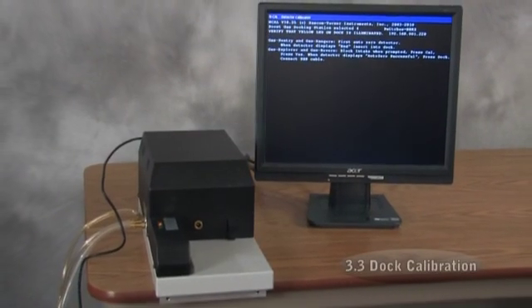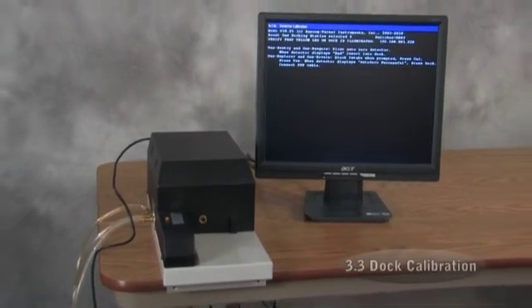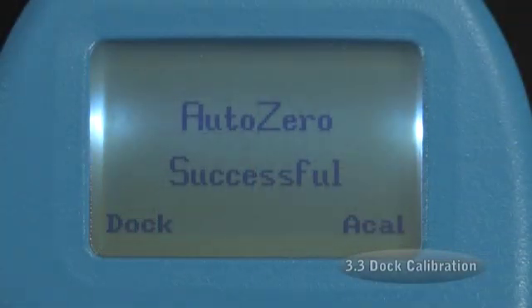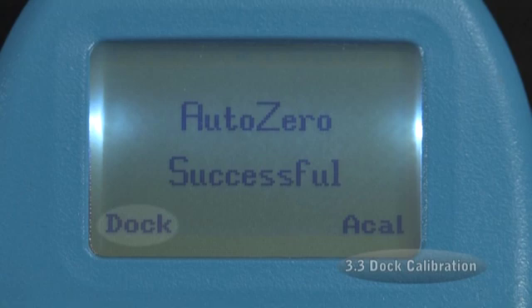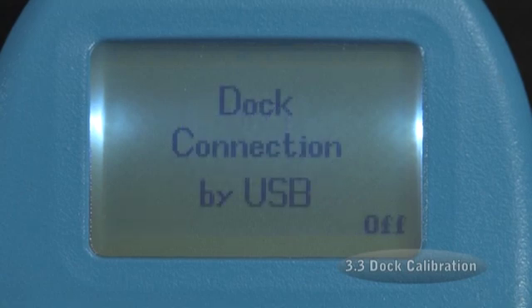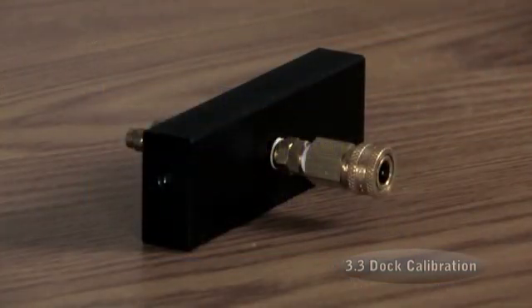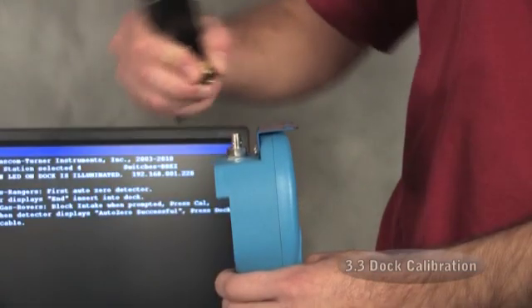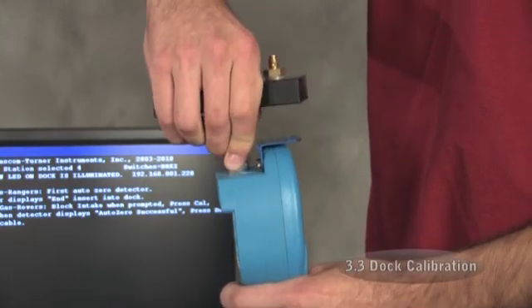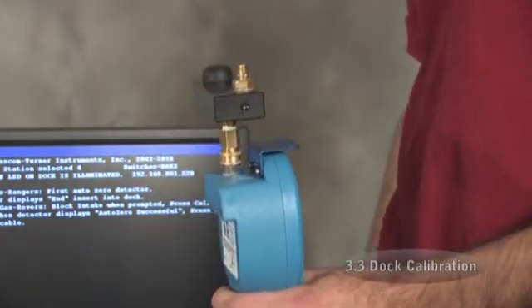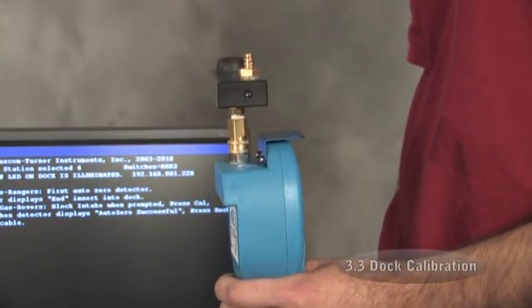Now we'll calibrate the Explorer using a docking station. Once the Auto Zero Successful screen appears, press the left button under the word Dock. You will see the message Dock Connection by USB. Connect the adapter block Quick Connect to the inlet of the Explorer and turn it so that the inlet fitting on the adapter is aligned with the port on the ACal dock.